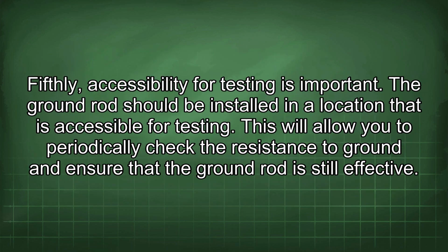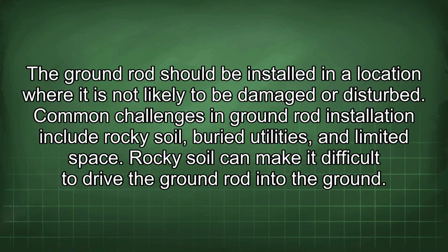Fifthly, accessibility for testing is important. The ground rod should be installed in a location that is accessible for testing. This will allow you to periodically check the resistance to ground and ensure that the ground rod is still effective. The ground rod should be installed in a location where it is not likely to be damaged or disturbed.